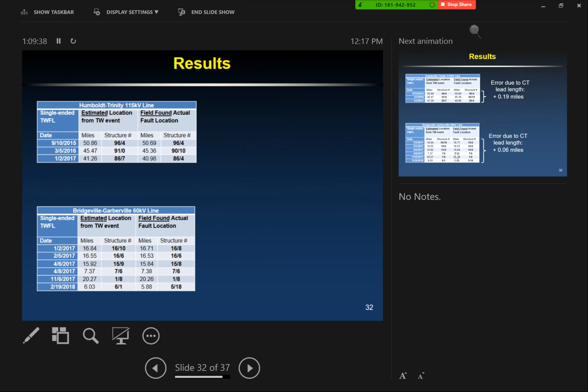This was our more complex 60 kV line, estimated location versus field found results. I can summarize it for you: we had one dead on, and we're off by 3 in our worst case, across 3 poles or structures.